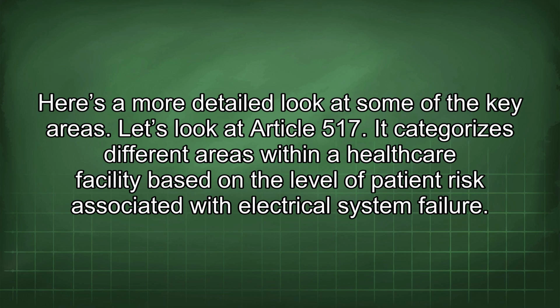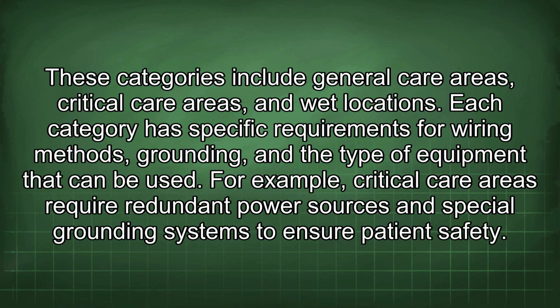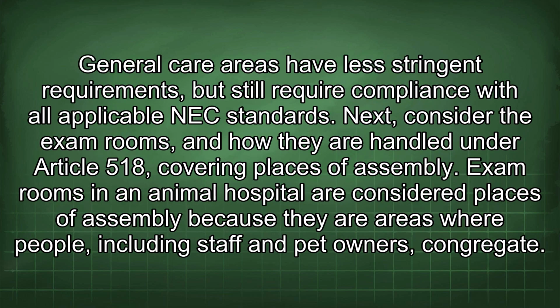Let's look at Article 517. It categorizes different areas within a healthcare facility based on the level of patient risk associated with electrical system failure. These categories include general care areas, critical care areas, and wet locations. Each category has specific requirements for wiring methods, grounding, and the type of equipment that can be used. For example, critical care areas require redundant power sources and special grounding systems to ensure patient safety. General care areas have less stringent requirements, but still require compliance with all applicable NEC standards.